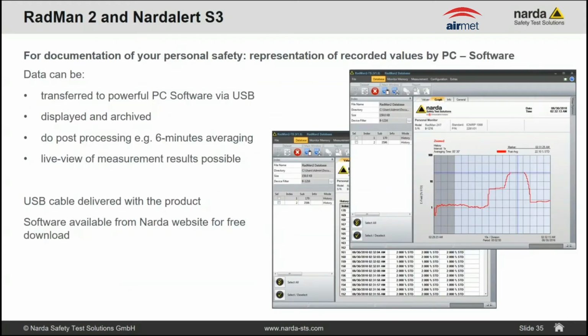PC software is available. For those of you who are already users of the NBM, it is based on our broadband meter software. It's a full database where you have access to all the results, which you can upload via USB to your PC, and you can set up different averaging methods and so on. It's also good for a functional test, because you also have a real-time measurement function, so that you see the curves in real time of the 3 magnetic sensors and the 3 electric sensors separately. So you can check the functionality of the probe systems, divided by electric and magnetic fields.